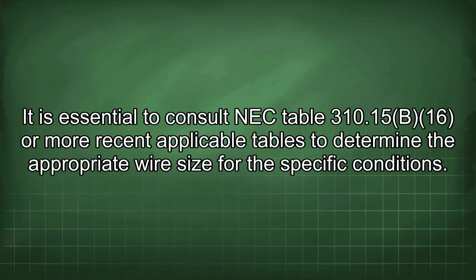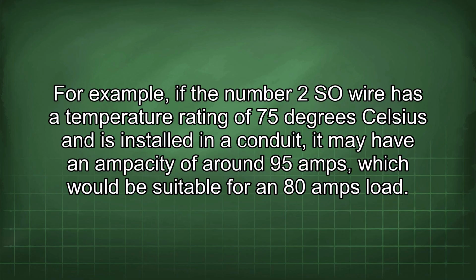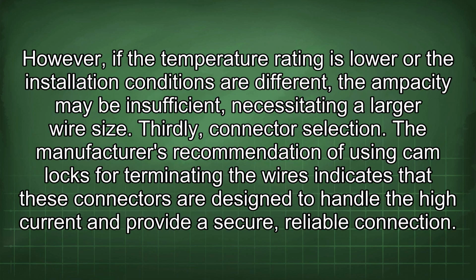It is essential to consult NEC Table 310.15(B)(16) or more recent applicable tables to determine the appropriate wire size for the specific conditions. For example, if the number 2 SO wire has a temperature rating of 75 degrees Celsius and is installed in a conduit, it may have an ampacity of around 95 amps, which would be suitable for an 80 amps load. However, if the temperature rating is lower or the installation conditions are different, the ampacity may be insufficient, necessitating a larger wire size.